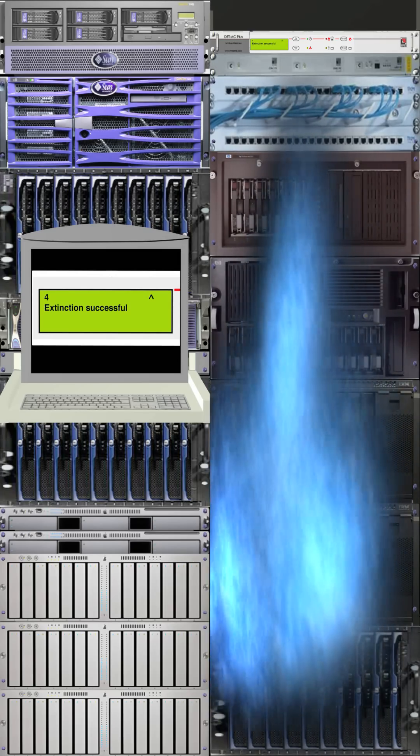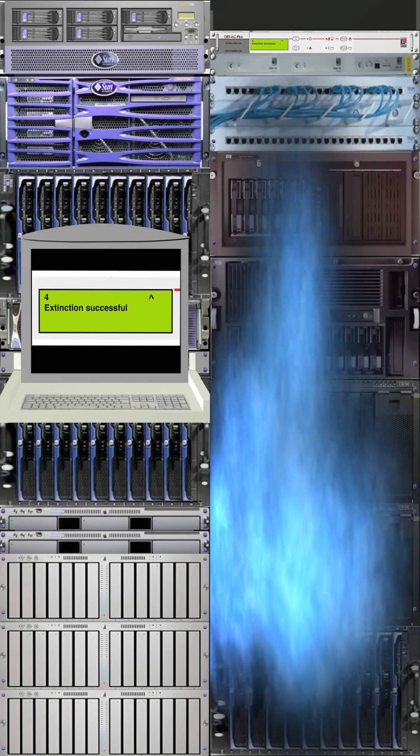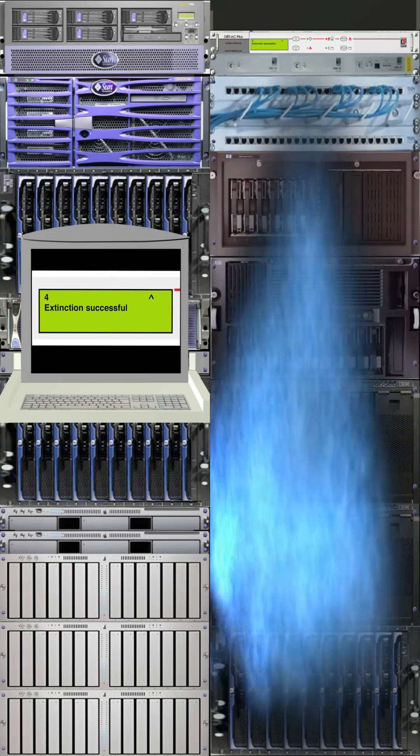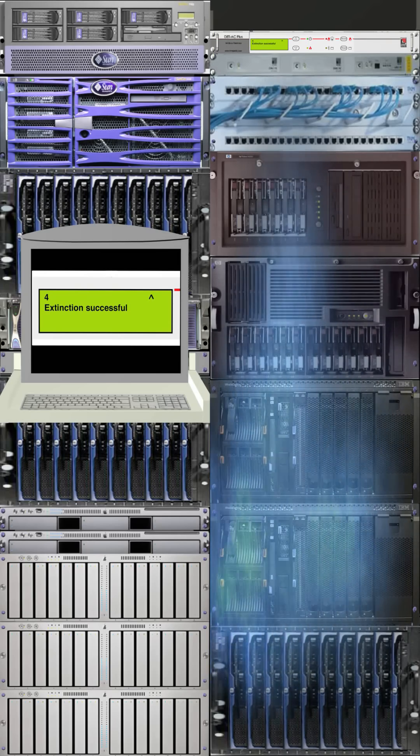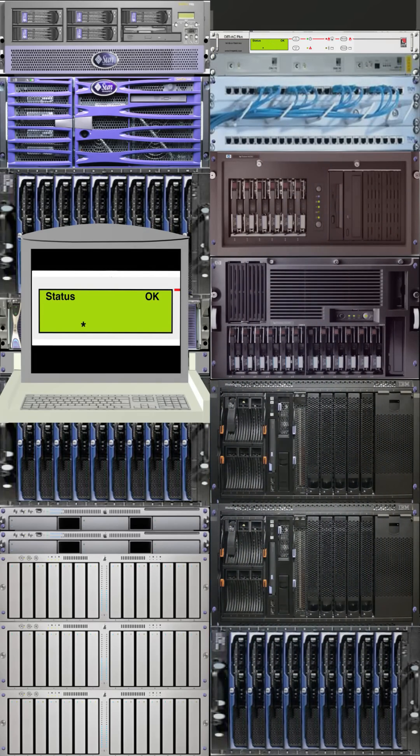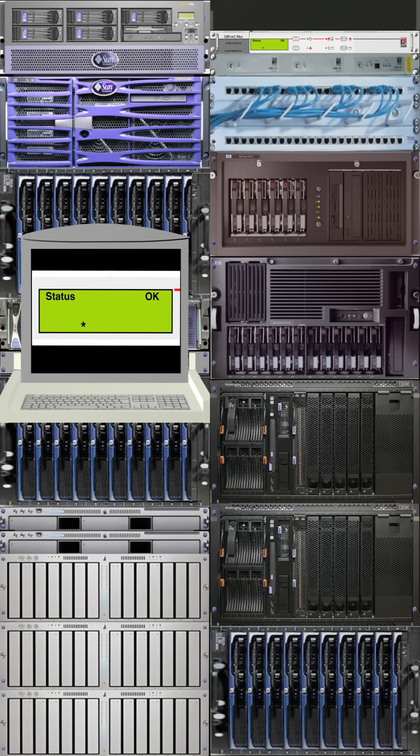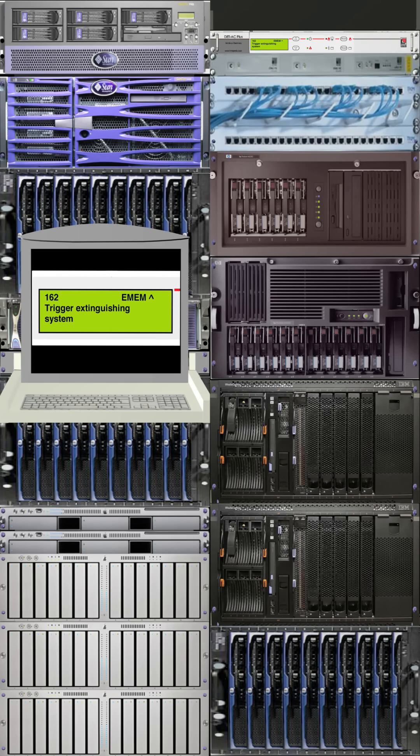Due to the rapid detection of smoke, even in racks with a high level of airflow, this ensures that there's plenty of time to forward an alarm message either acoustically, optically via the liquid crystal display, or by connecting the volt-free contacts to the building management system or fire alarm center.